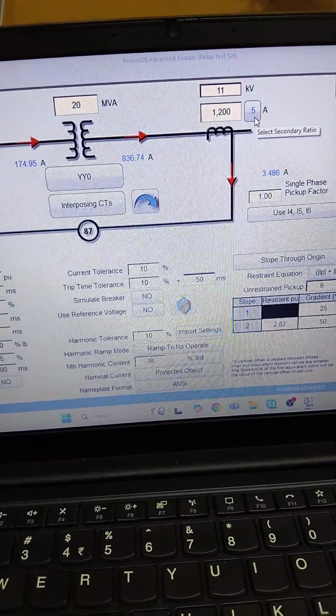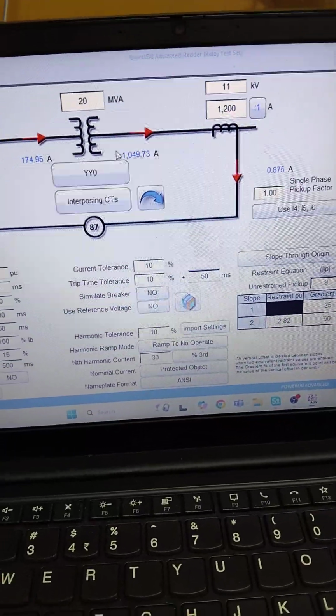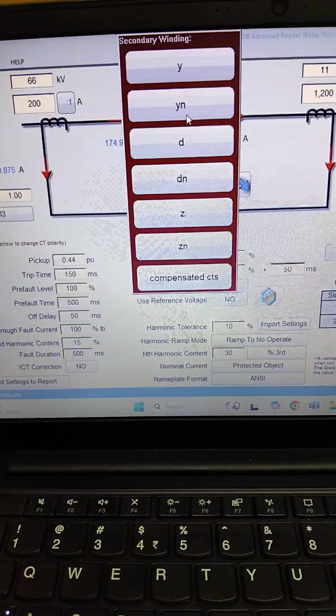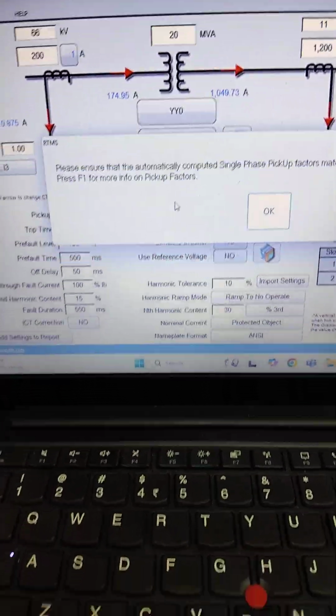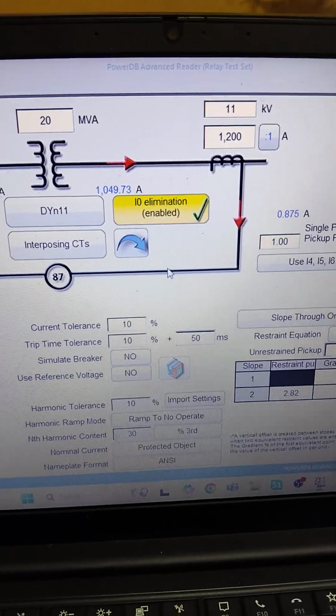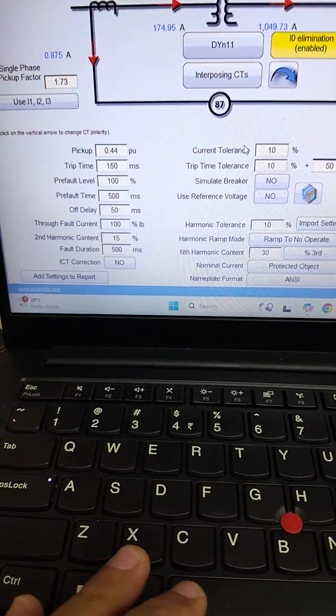This is 11 kV bar, 1200/1 CT ratio. So select it, and vector group is DYN11. So just choose DYN11 and that's it. It will automatically enable the zero sequence filtration. Now for settings, you don't need to set it manually.